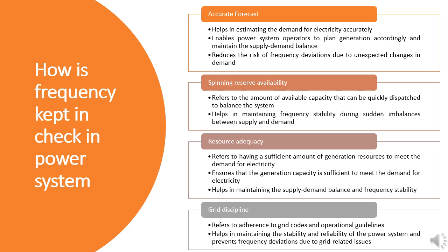Spinning reserve availability is another key factor in maintaining frequency stability during sudden imbalances between supply and demand. Spinning reserve refers to the amount of available capacity that can be quickly dispatched to balance the system. Resource adequacy refers to having a sufficient amount of generation resources to meet the demand for electricity, helping to maintain the supply-demand balance and frequency stability. Grid discipline is also essential — adherence to grid codes and operational guidelines helps prevent frequency deviations. By ensuring that all system operators follow the same rules and procedures, grid discipline helps maintain consistency and stability in the power system.